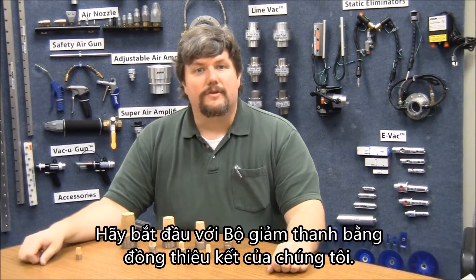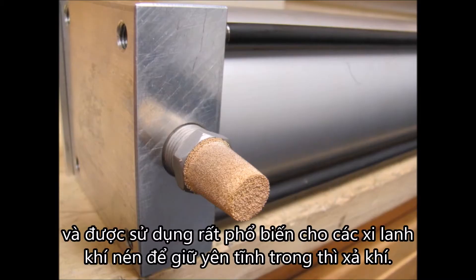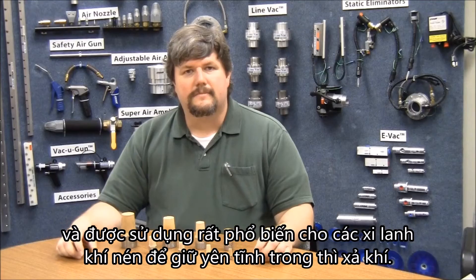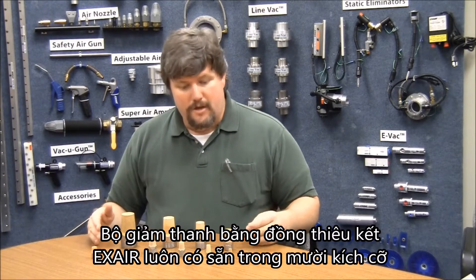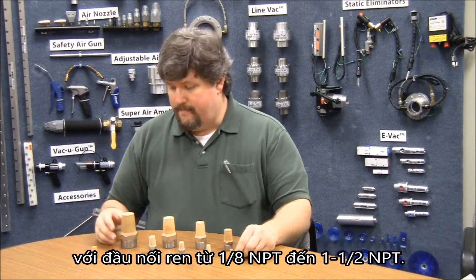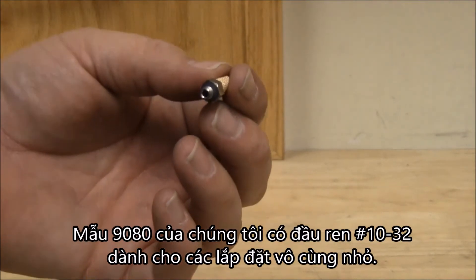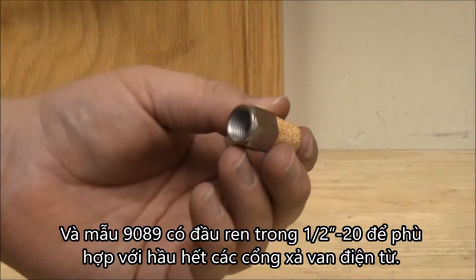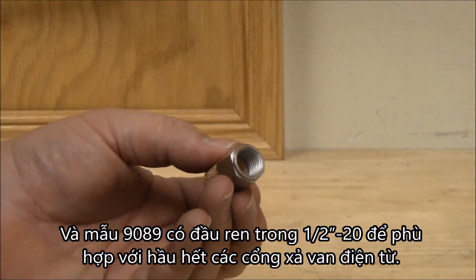Let's start with our sintered bronze mufflers. These simple, low-cost mufflers are easy to install and are very popular for use with air cylinders to quiet the exhaust stroke. EXAIR sintered bronze mufflers are available in 10 sizes with threads from 1/8 inch NPT to 1/2 inch NPT. Our model 9080 has 10-32 threads for very small installations, and the model 9089 has 1/2-20 female straight threads to fit most solenoid valve exhausts.